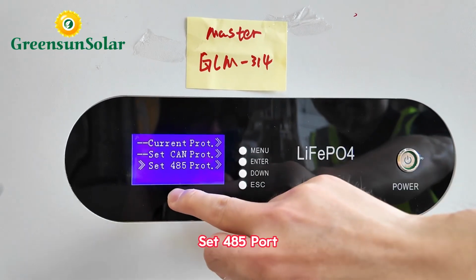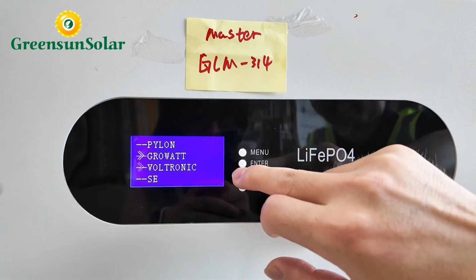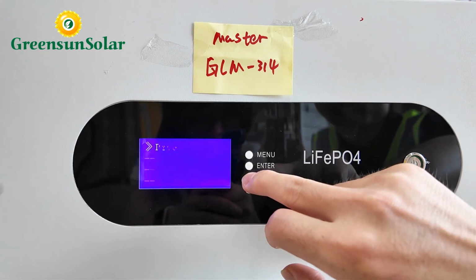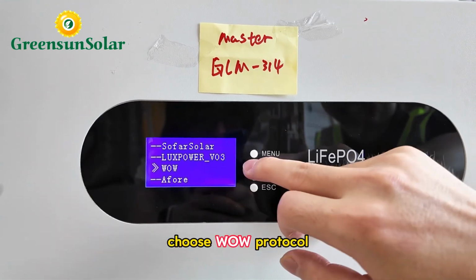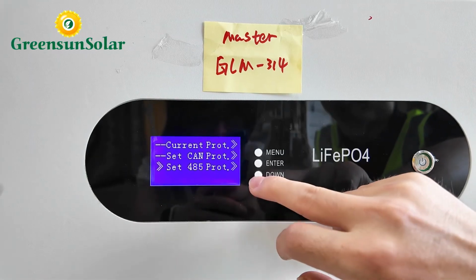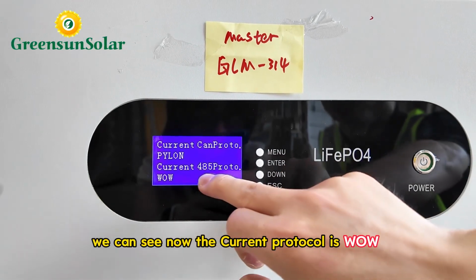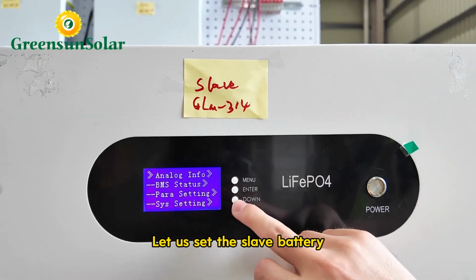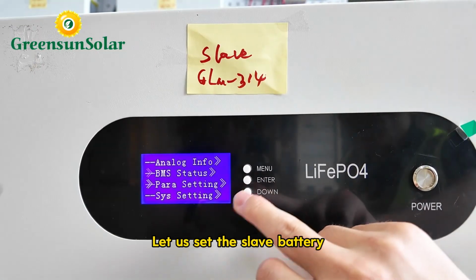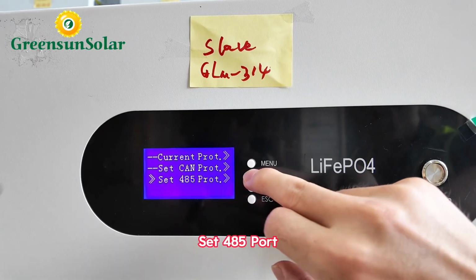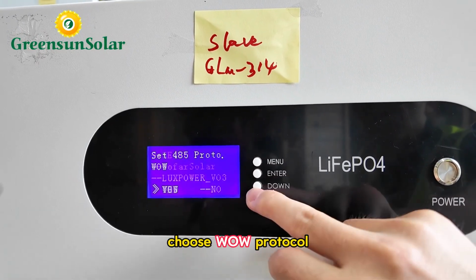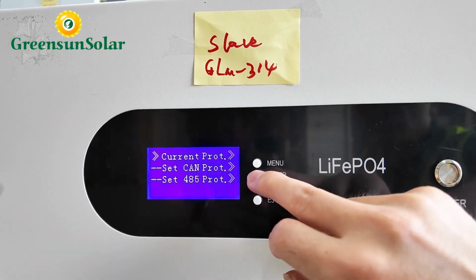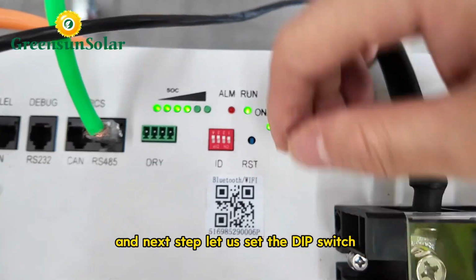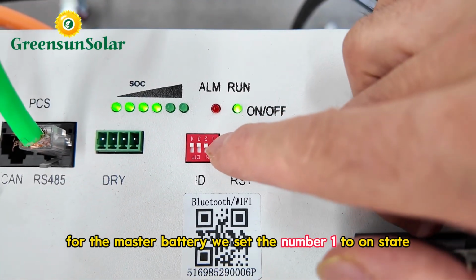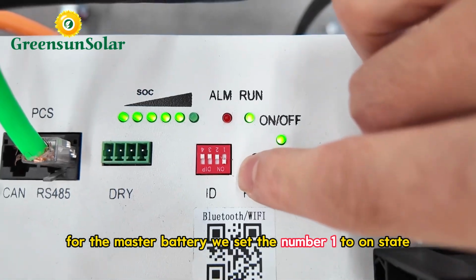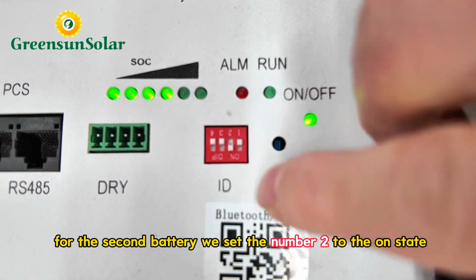Just enter and set the RS485 port. Choose the WOW protocol. Yes. You can see now the current protocol is WOW. Let us set the slave battery. And next step, let us set the DIP switch. For the master battery, we set the number 1 to the on state. For the second battery, we set the number 2 to the on state.